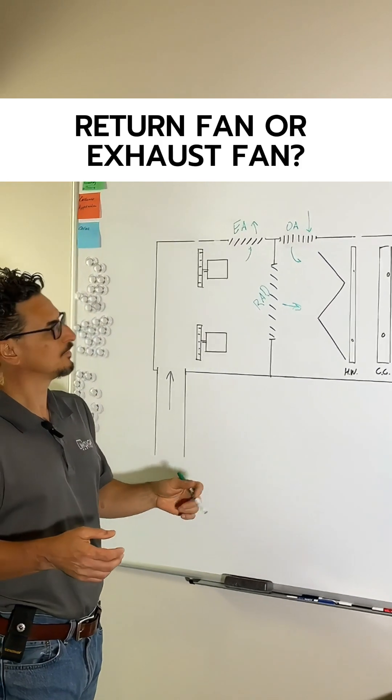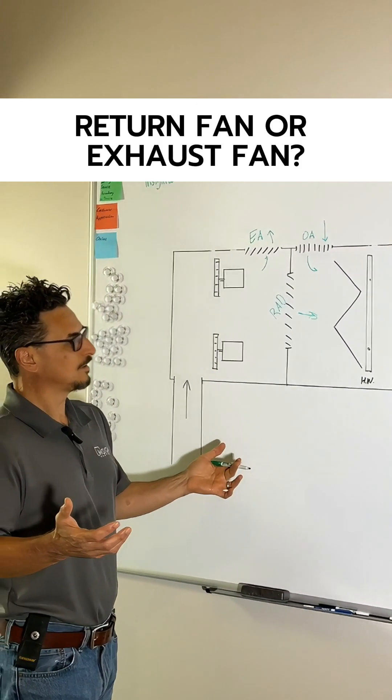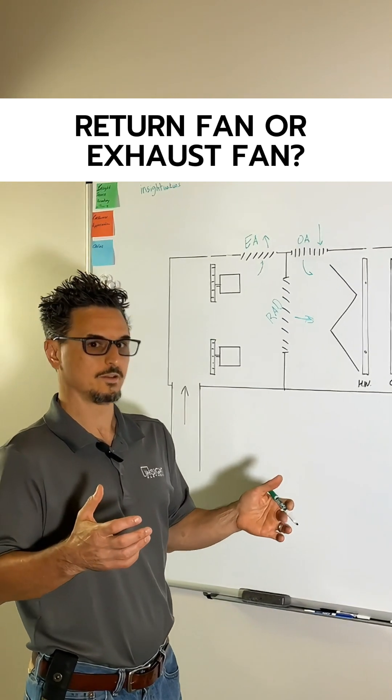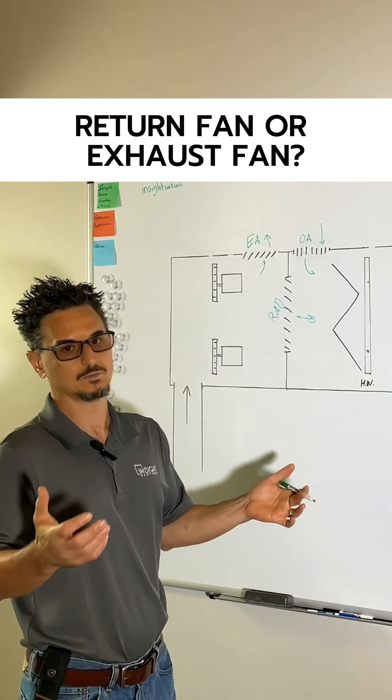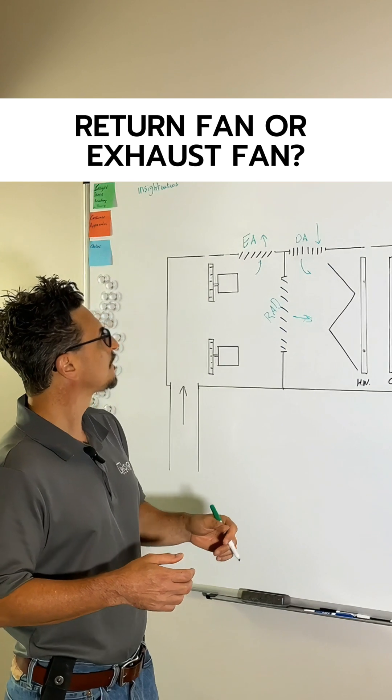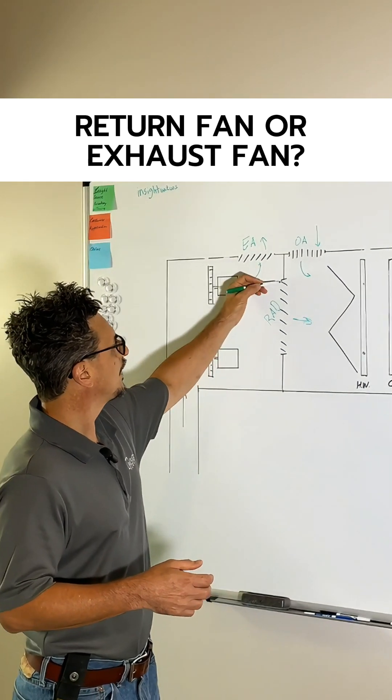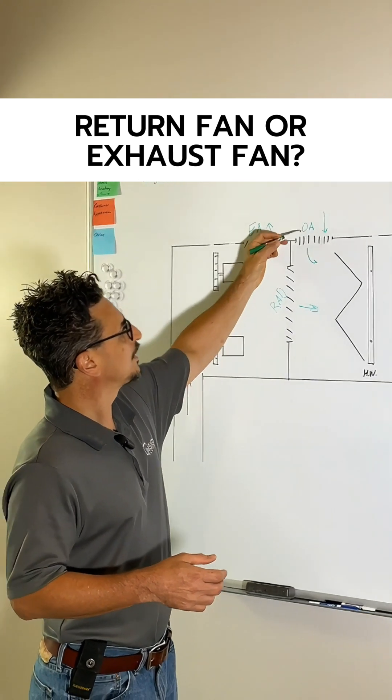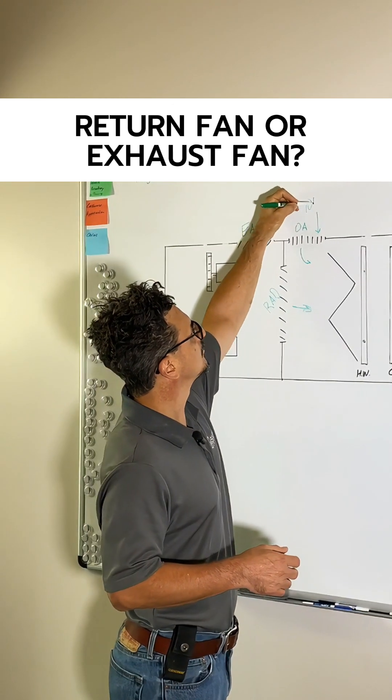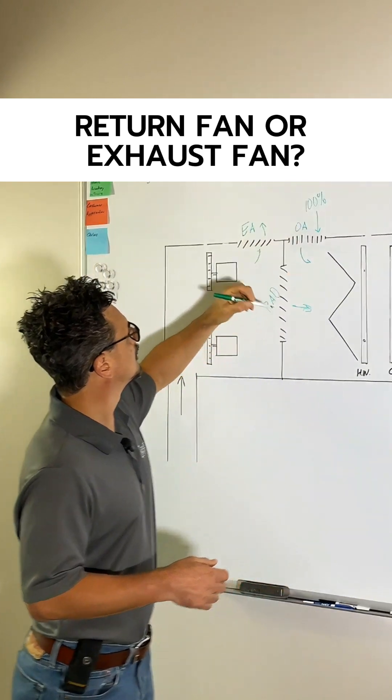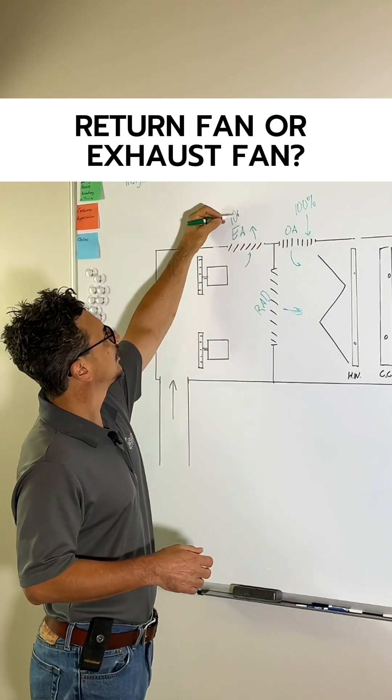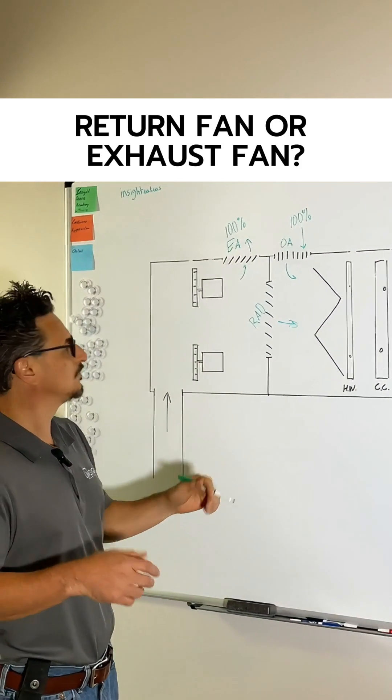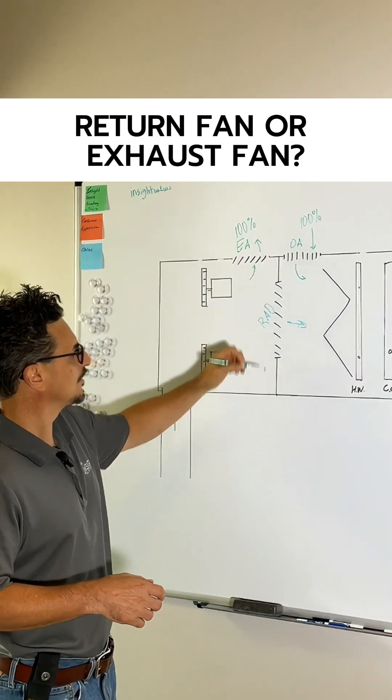20% outside air-ish or whatever. So the great thing about this is when you have an economizer scenario. Let's say you have 55 degrees outside, it's a beautiful low dew point day. What you can do is close this return air damper, okay, just close this off and bring in 100% outside air and exhaust. 100%-ish, you know, you want to keep the building positively pressurized, but you get the gist there. So this will be completely closed off in that scenario.